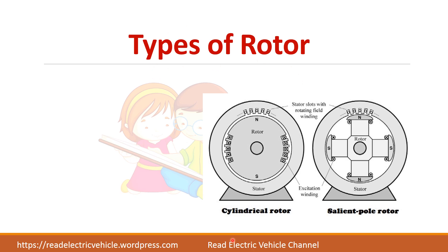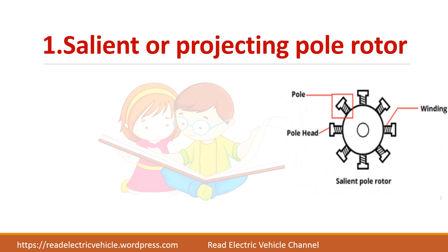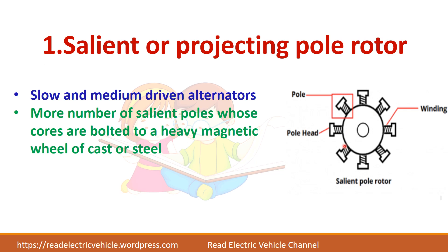There are two types of rotors: one is the salient pole rotor and the other is called a cylindrical rotor. Salient means projecting — you can see the poles are projecting outward. Depending upon the requirement, we can use the salient pole rotor or the cylindrical rotor. The salient pole rotor is used for slow and medium speed driven alternators, with projecting poles attached to a wheel-like structure.